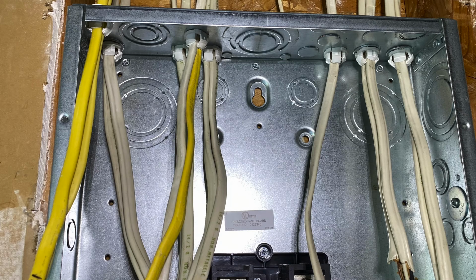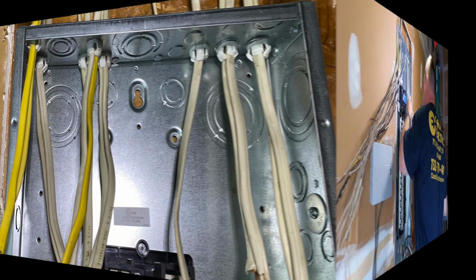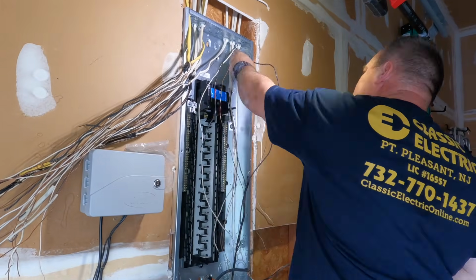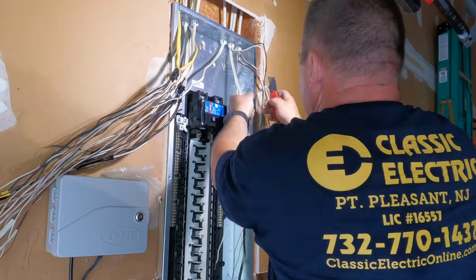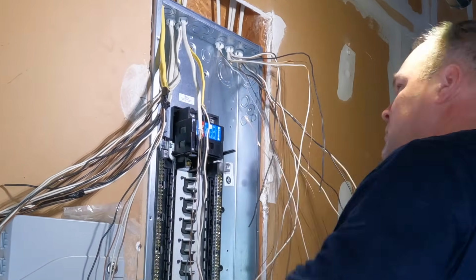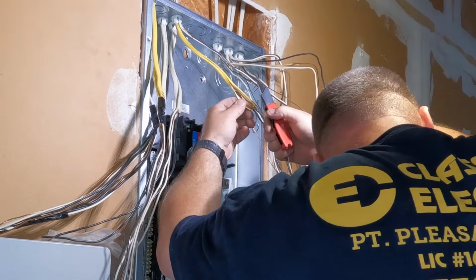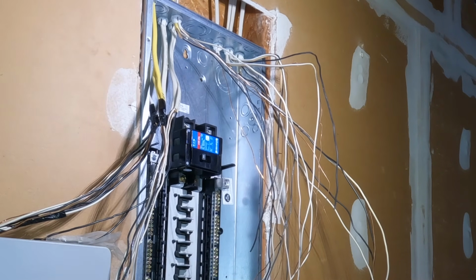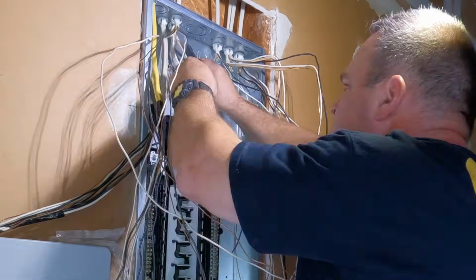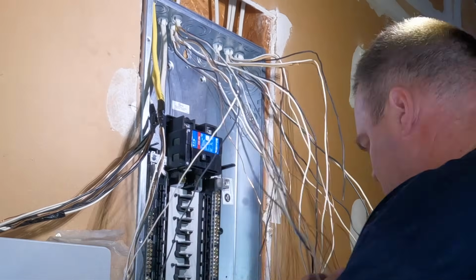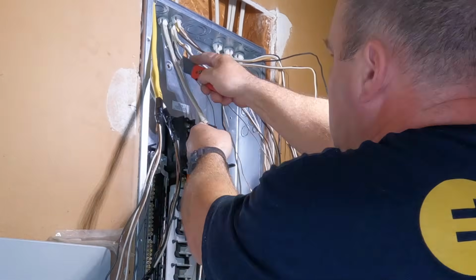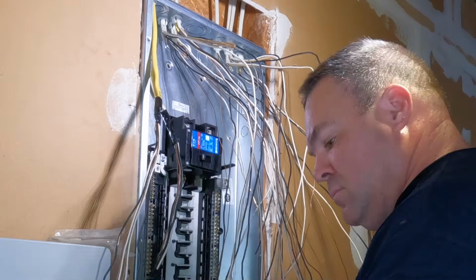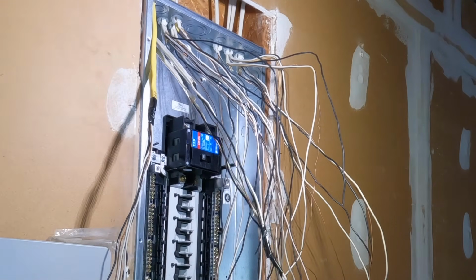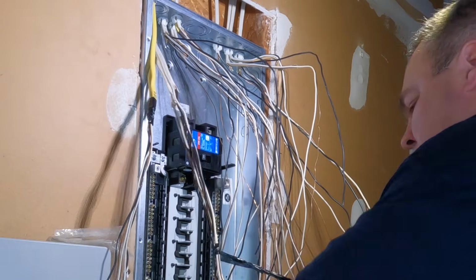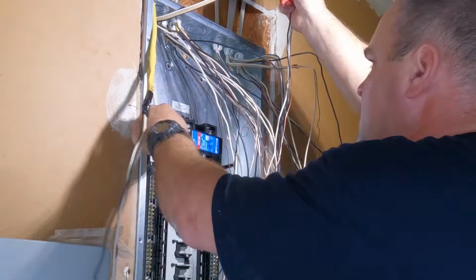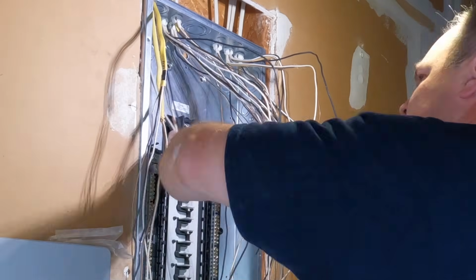But anytime I've got Romex and I'm changing the panel, in my opinion, that's super simple compared to some of those old houses with the armored cable BX stuff. Those can take a long time if you have a lot of circuits with BX cables. So now I'll strip them back and isolate my grounds, neutrals and hot conductors. These are all 120 volt circuits up there. So separate the bare grounds, separate the whites, separate the blacks, and individually terminate all of them.